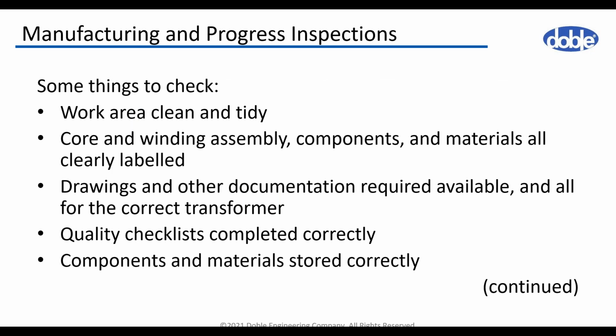Some things we check during the progress inspection include the working area. Is it clean, tidy? This is sometimes underestimated by the manufacturers, but you cannot expect a dirty, messy area and at the same time an active part which is clean with no contaminations. We expect all the components, materials, as well as the core and winding assembly to be clearly identified. The drawings for the unit we inspect and the documentation required should be available, and for the correct transformer.